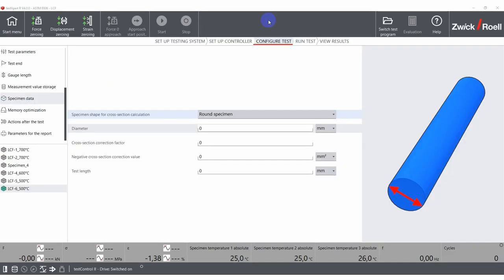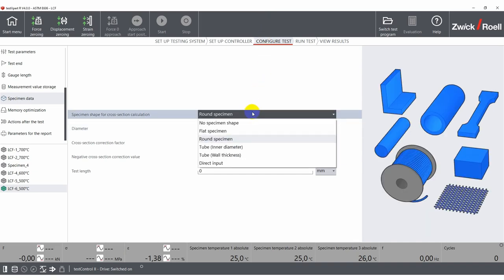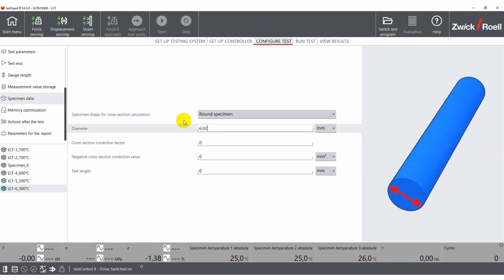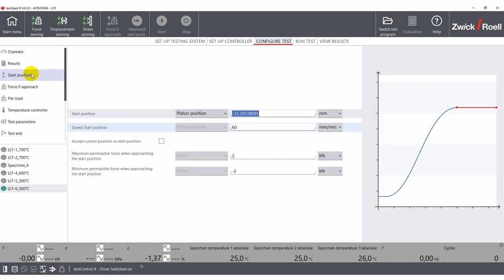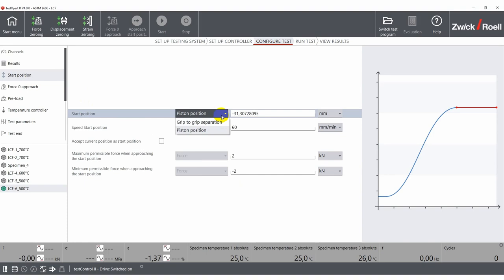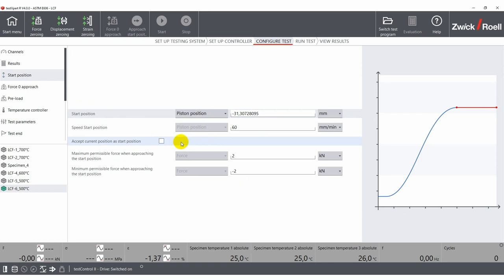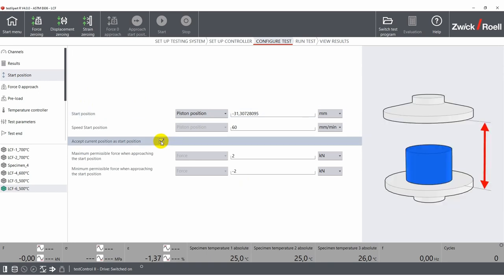To configure an LCF test according to ASTM E606, the user first enters the specimen shape and dimensions. The user then defines the start position for the test, which can be fixed grip-to-grip separation or a fixed piston position. You also have the option to start the test at your current start position.